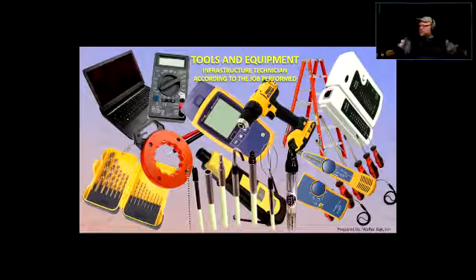All right. Now, right beside here, a little bit to the left, we have something that's called a fish tape. Right. What do we use the fish tape for? It's a steel tape that is rolled up into a bundle, and you can get some shorter ones, maybe 40 footers, 60 footers. 100 feet is probably towards the longest ones, because to be honest, you can shove the fish tape into a conduit, and if it gets more than 100 feet, you can keep pushing it and it's going to start binding on you, right? So up to 100 feet is probably the most practical solution for the fish tape.